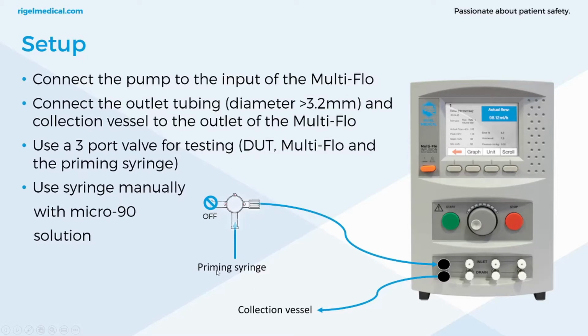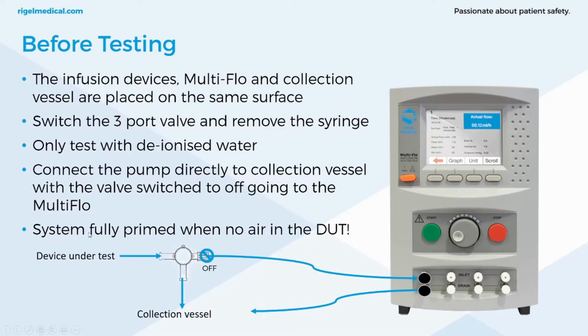So with this priming syringe through to the infusion device to the collection vessel, that's it, using the priming menu selection. Then after that, we've done our priming. Also again, it recommends the micro 90. I can't reiterate that enough. Again, the infusion device, Multi-Flo and collection vessel are then placed on the same surface. Always ensure this. We can now switch the 3-port valve and remove the syringe.